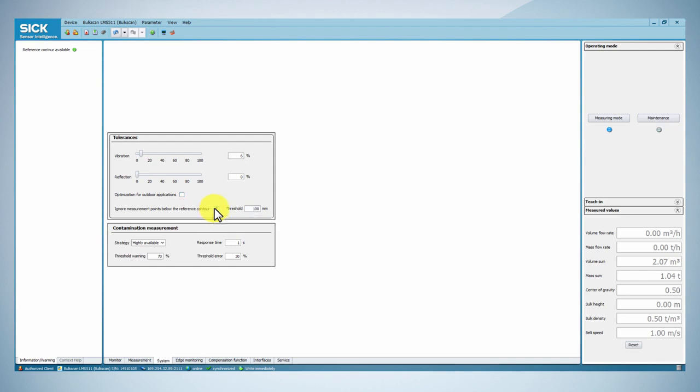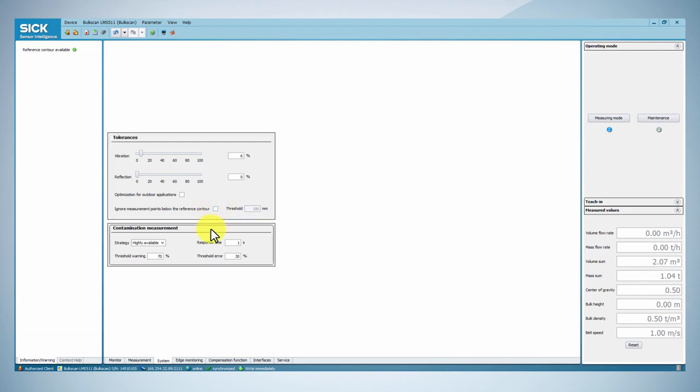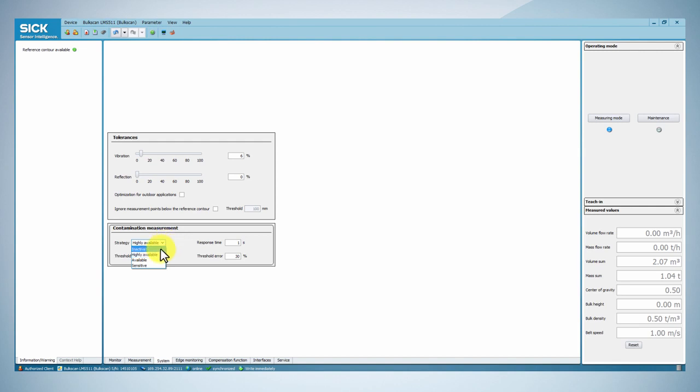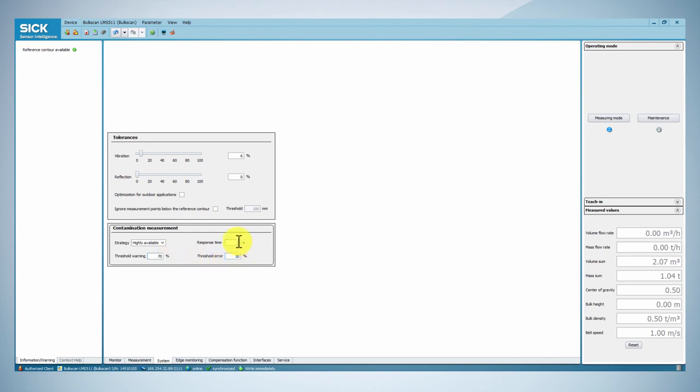If the conveyor belt has slits or gaps, you can activate the function Ignore measurement points below the reference contour. The contamination measurement box contains the settings for the level of contamination of the screen of the sensor that can be accepted. Change this accordingly to the environment of the installation if necessary.